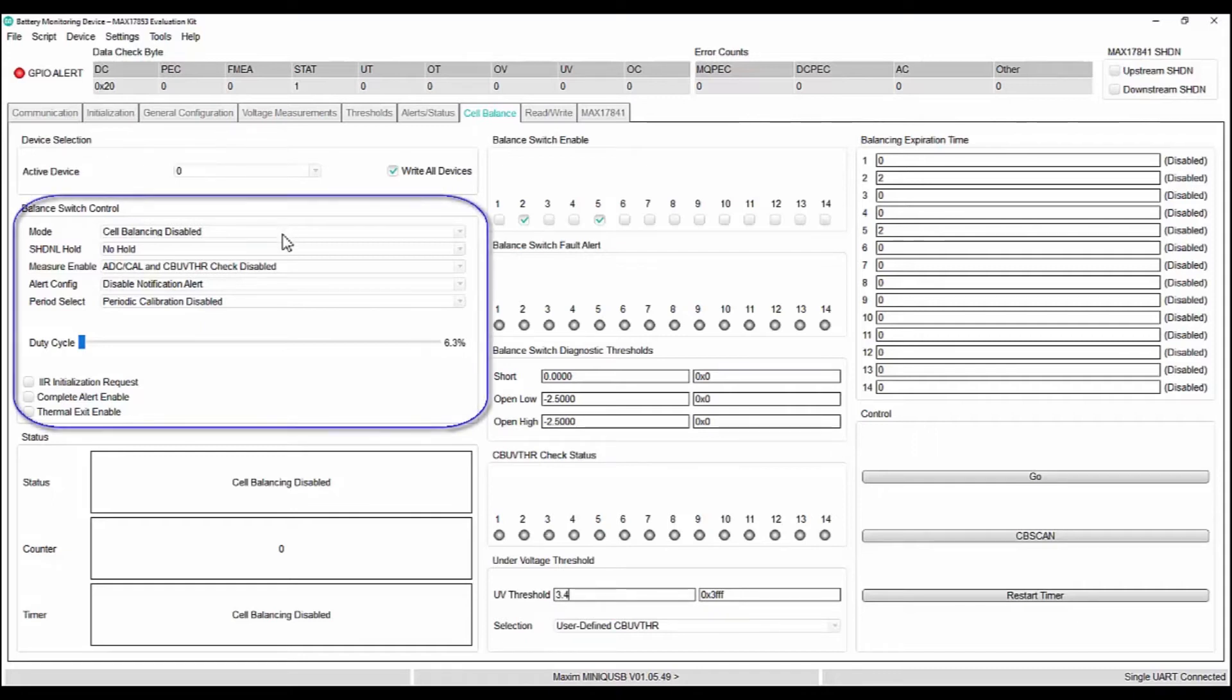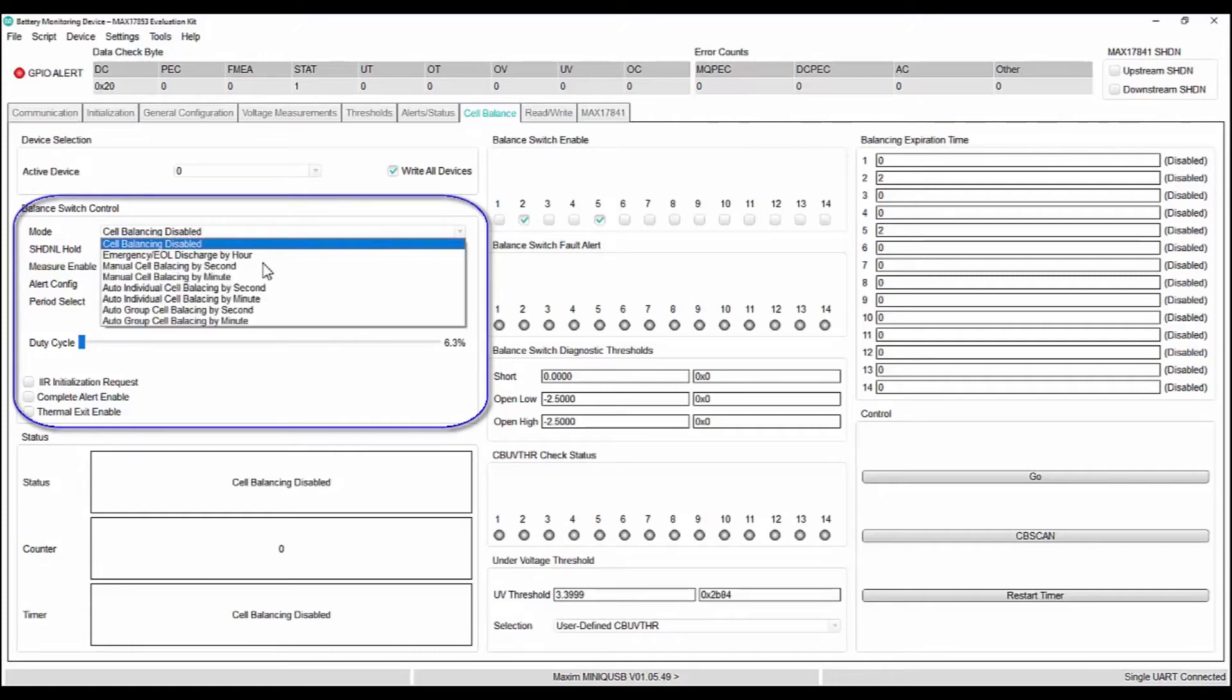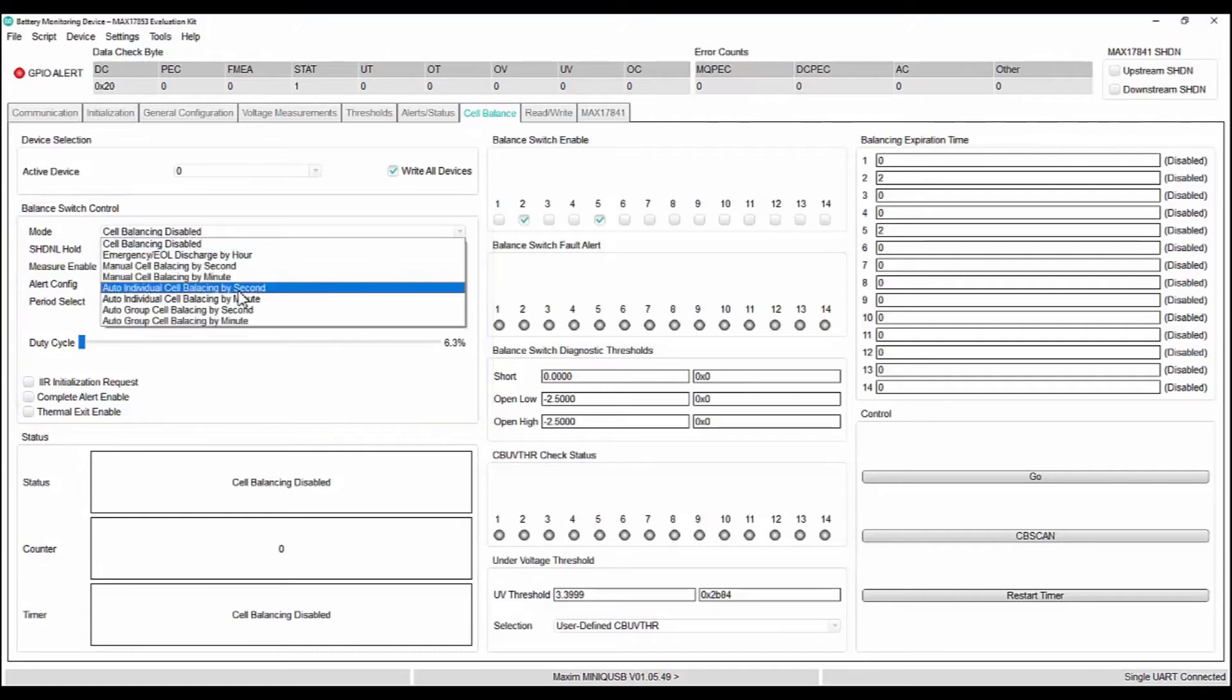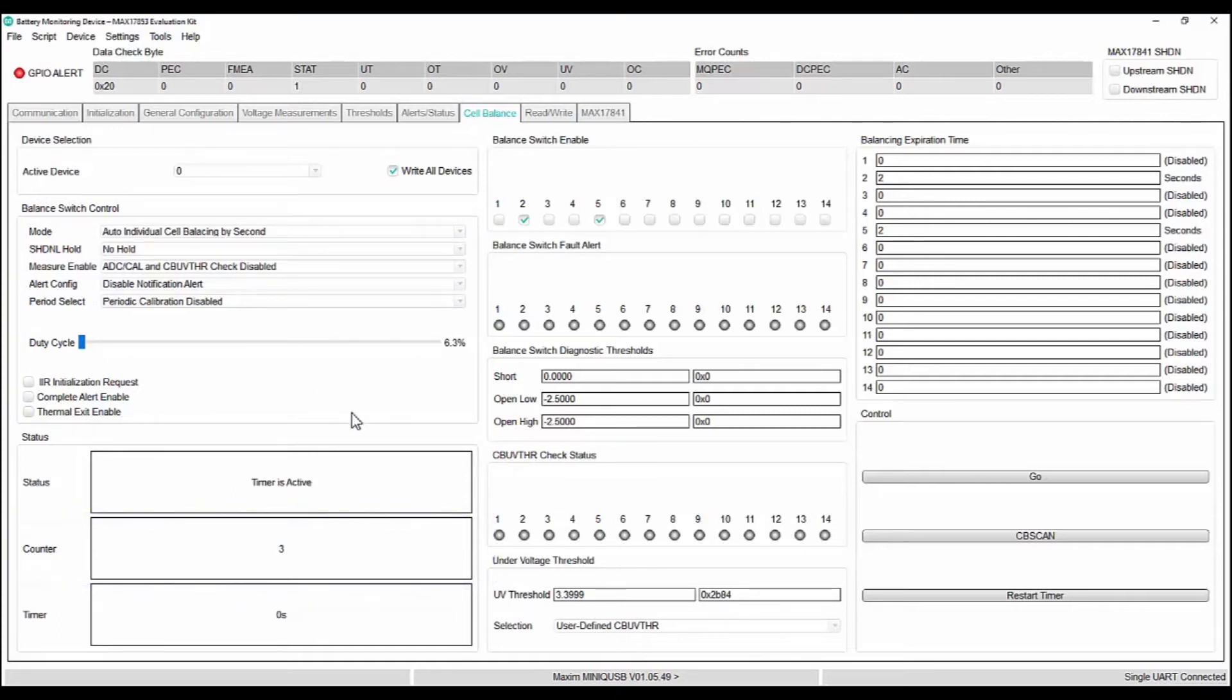Select the auto cell balancing by seconds. You can see the counter starts and the selected cells are being balanced. Auto cell balancing stops the balancing if there is a balance time expiry or the voltage reaches below the under voltage threshold.